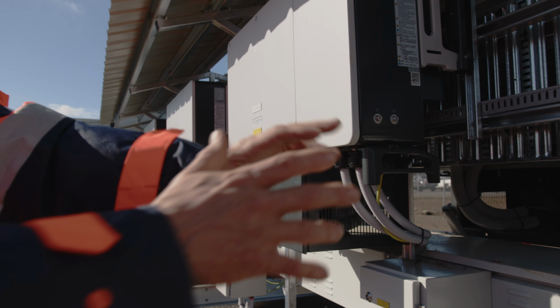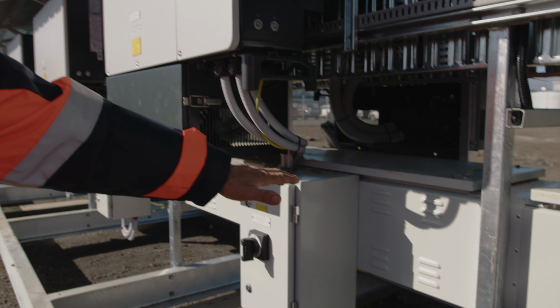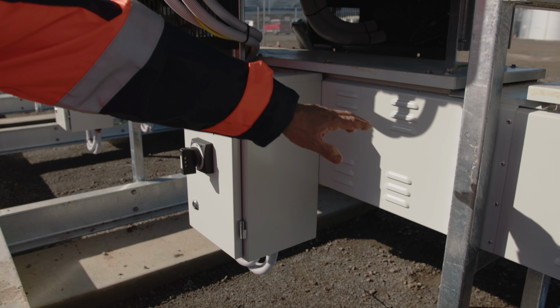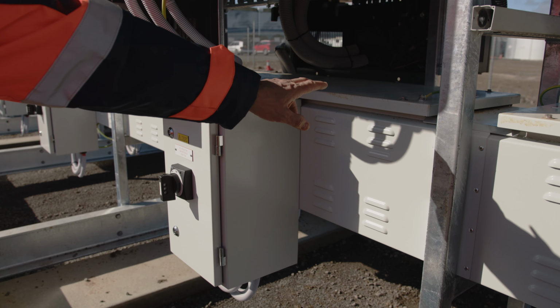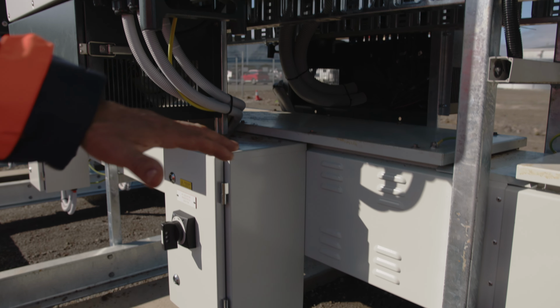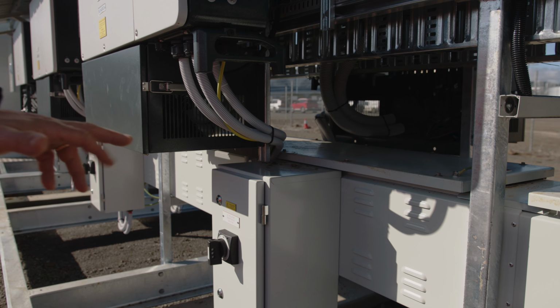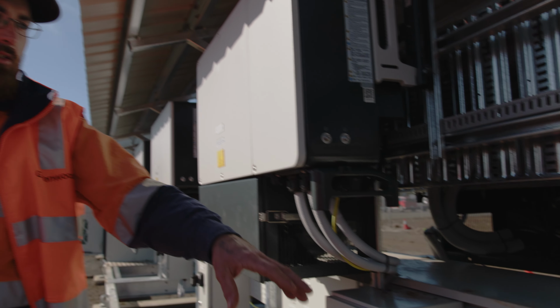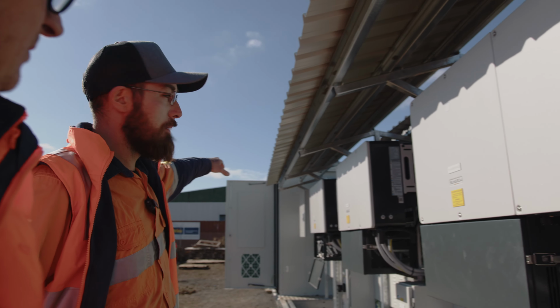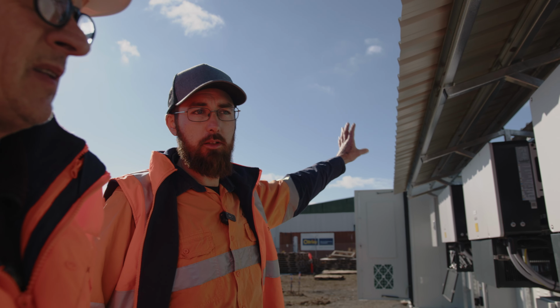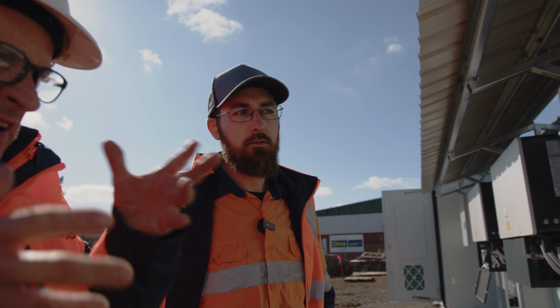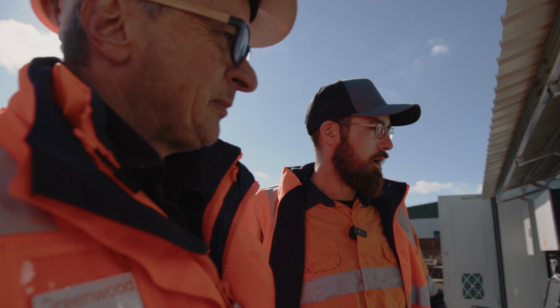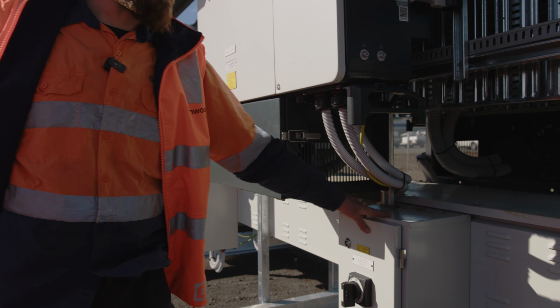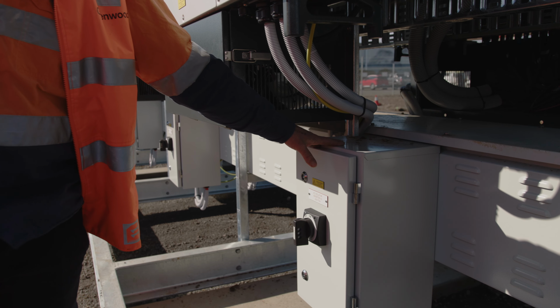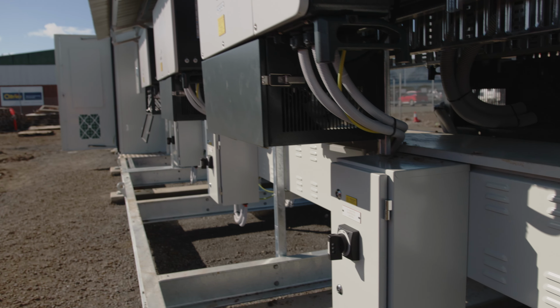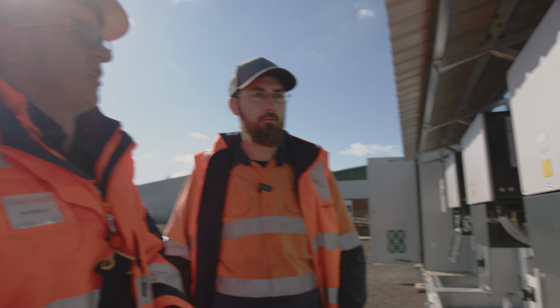Alex, we're right in between the inverters, and we've got this kind of enclosed area here, and there's a lid, and I can see some earthing, there's a danger sign. What is accommodated, what's contained inside there? This is a bus duct. So this has bus bars that connect directly back to our main switch inside the main switchboard at the end of the skid. So this is where all the inverters basically come in? That's correct. So each one of these circuit breakers connects directly back into the bus duct and onto a bus bar. So we'll talk a little bit more about the AC isolators and the enclosures here.